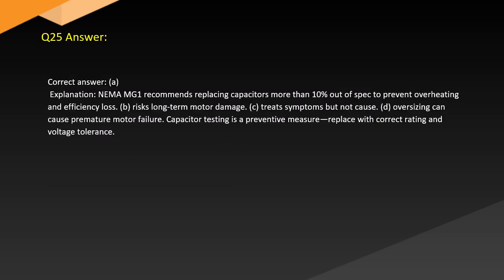Answer. Correct answer: A. Explanation. NEMA MG1 recommends replacing capacitors more than 10% out of spec to prevent overheating and efficiency loss. B. Risks long-term motor damage. C. Treats symptoms but not cause. D. Oversizing can cause premature motor failure. Capacitor testing is a preventive measure. Replace with correct rating and voltage tolerance.